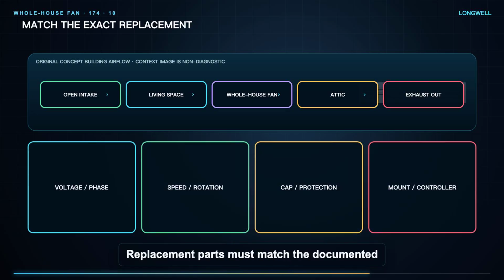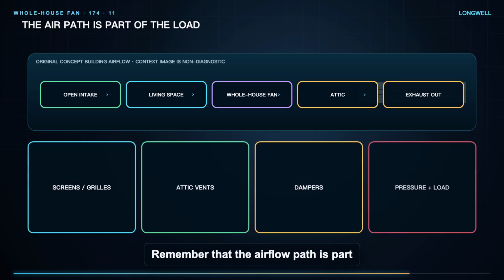Replacement parts must match the documented electrical and mechanical requirements. Voltage, frequency, phase, speed, capacitor value, rotation, mounting, belt geometry, thermal protection, controller compatibility, and environmental rating can all matter. Similar appearance is not an engineering match. Remember that the airflow path is part of the load.